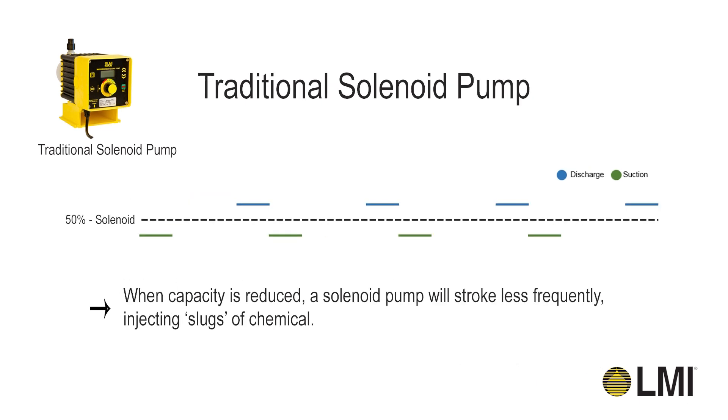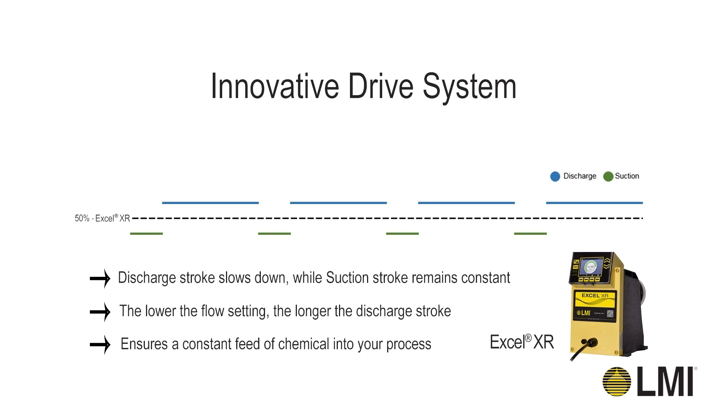On a solenoid pump, as you turn down the capacity, the pump strokes less frequently, so it's pushing a full stroke of chemical into the system quickly at less frequent intervals as capacity is turned down. As the Excel XR's capacity is turned down, the discharge stroke slows down while the suction stroke remains constant. This ensures a constant feed of chemical into your process.